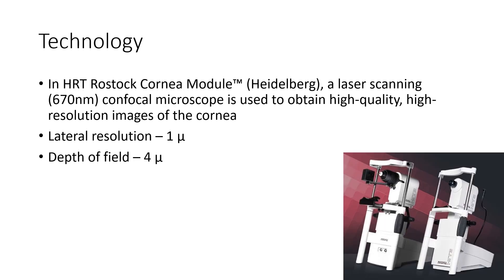Coming to the technology of confocal microscopy. In the HRT Rostock cornea module manufactured by Heidelberg, a laser scanning confocal microscope of wavelength 670 nanometers is used to obtain high quality, high resolution images of the cornea. This picture shows the confocal microscope manufactured by Heidelberg. The lateral resolution is 1 micron and the depth of field is 4 microns.